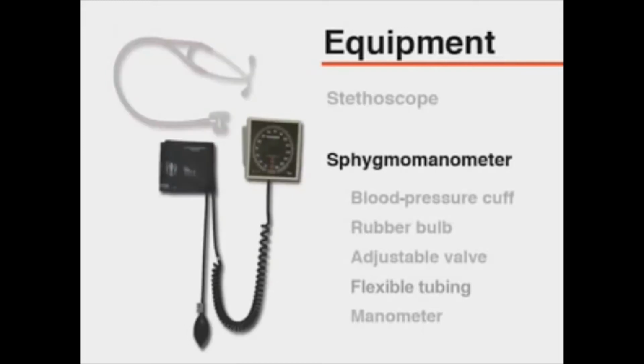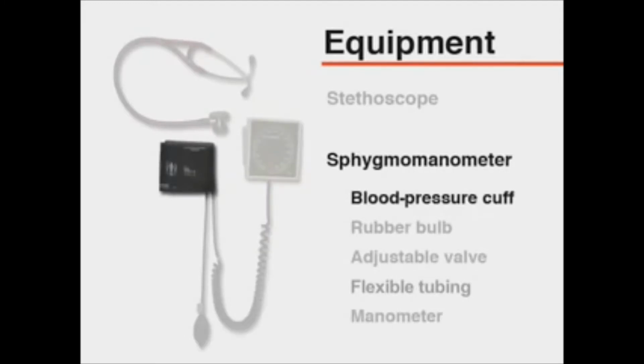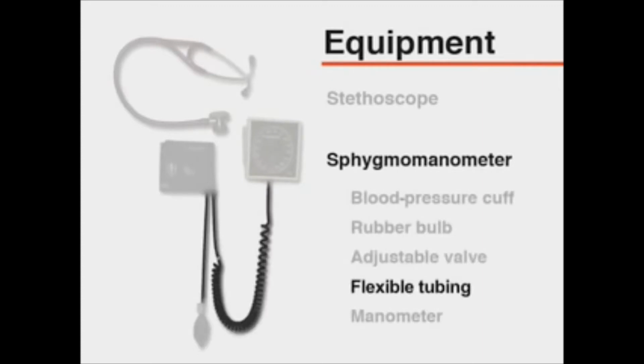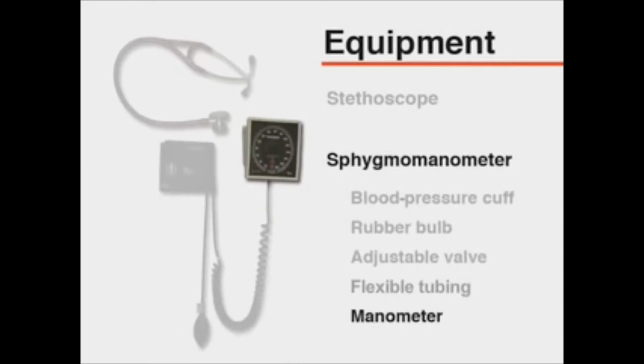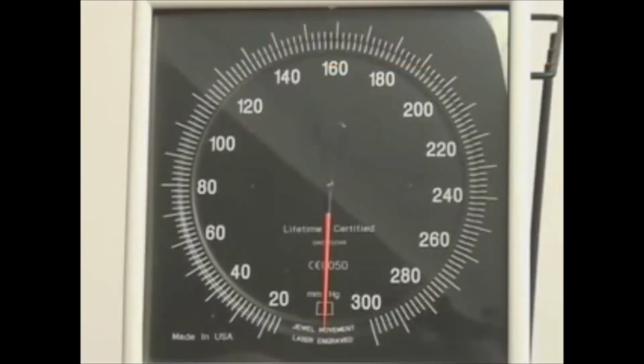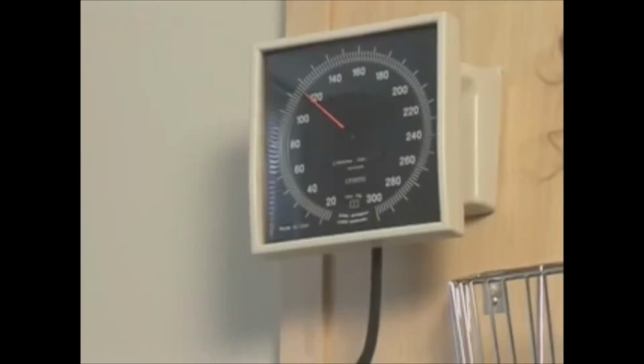A sphygmomanometer consisting of a blood pressure cuff containing a distensible bladder, a rubber bulb, and an adjustable valve, as well as flexible tubing. Finally, a manometer that documents the level of pressure within the cuff. Each part of the sphygmomanometer should be examined on a regular basis. The needle on an aneroid manometer should rest at 0 before and after measuring blood pressure.